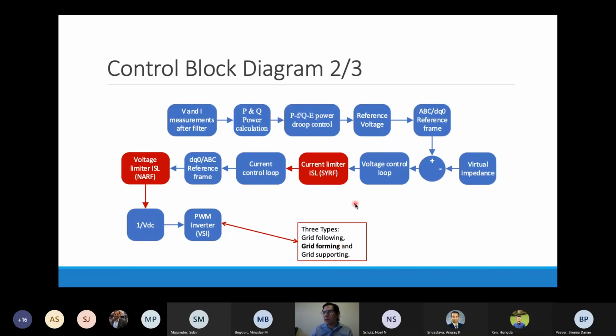Here I'm showing the control block of our inverter. Basically, we take the measurements of the voltage and current after the filtering. We calculate the different power, active and reactive power. We apply the droop control for the frequency and the voltage reference in order to create a reference of voltage.